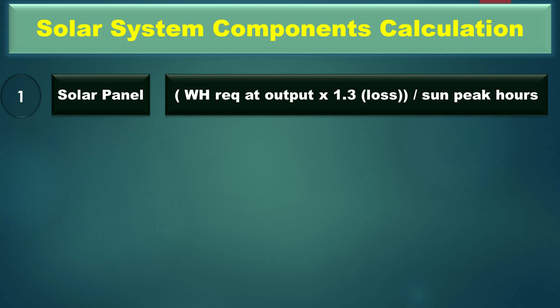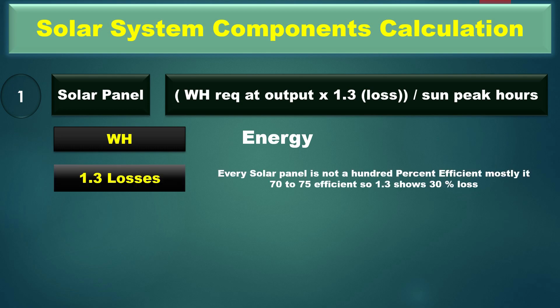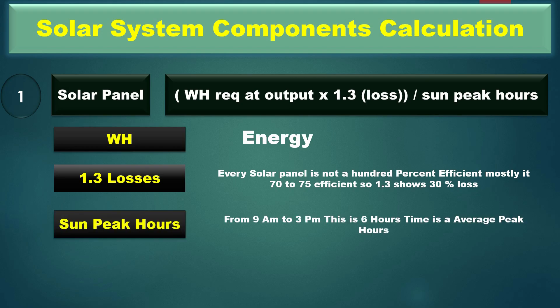First, we calculate the solar panel. The formula for solar panel is: watt-hours required at output multiplied by 1.3, divided by sun peak hours. Watt-hours required at output means energy, and we know the energy value is 9186. The 1.3 factor accounts for losses — solar panels are not 100% efficient; mostly they are 70 to 75% efficient, so 1.3 represents 30% losses.